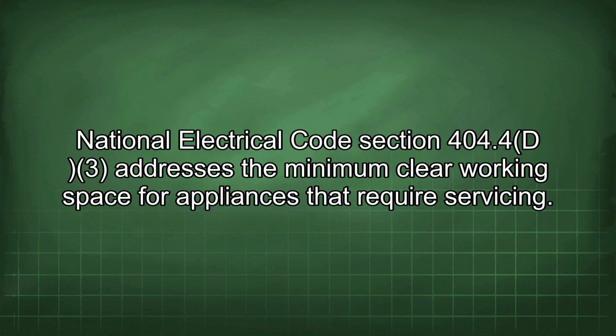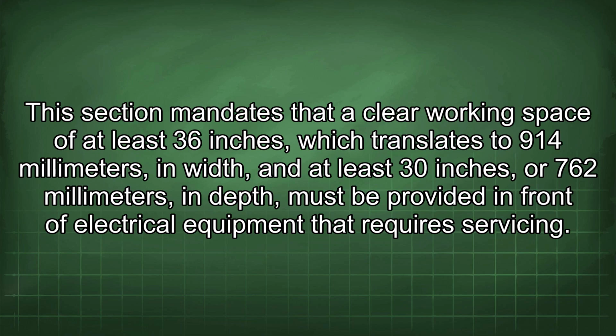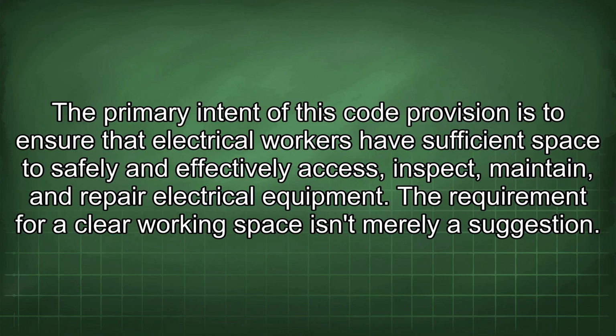National Electrical Code Section 404.4D3 addresses the minimum clear working space for appliances that require servicing. This section mandates that a clear working space of at least 36 inches, which translates to 914 millimeters in width, and at least 30 inches, or 762 millimeters in depth, must be provided in front of electrical equipment that requires servicing. The primary intent of this code provision is to ensure that electrical workers have sufficient space to safely and effectively access, inspect, maintain, and repair electrical equipment.